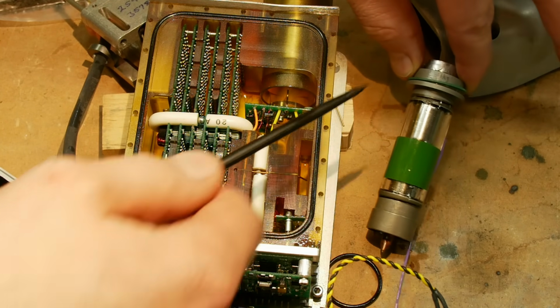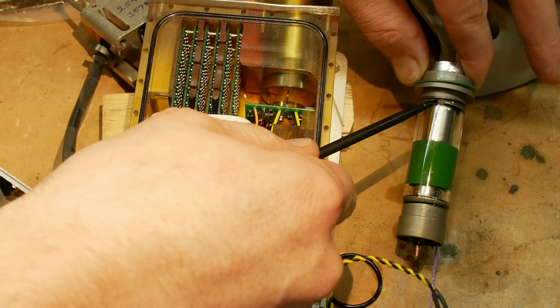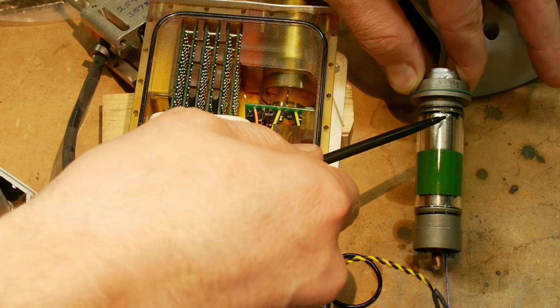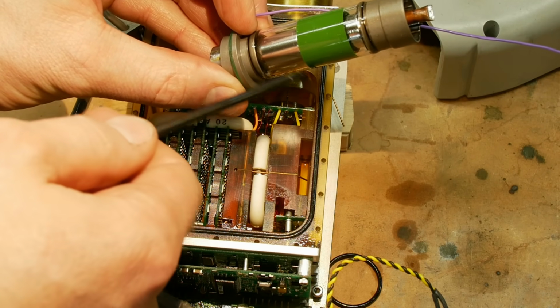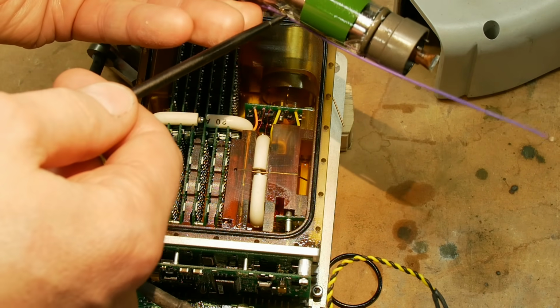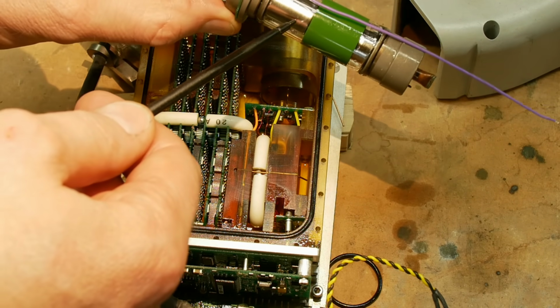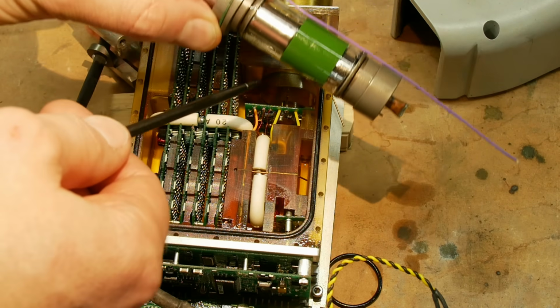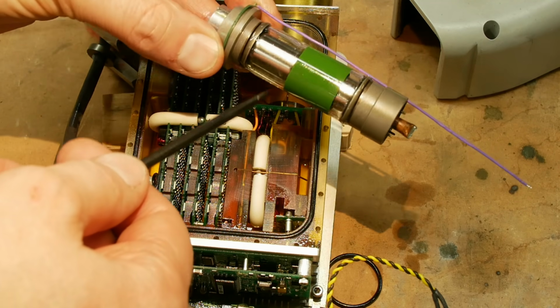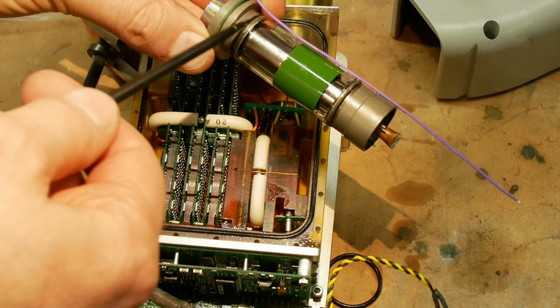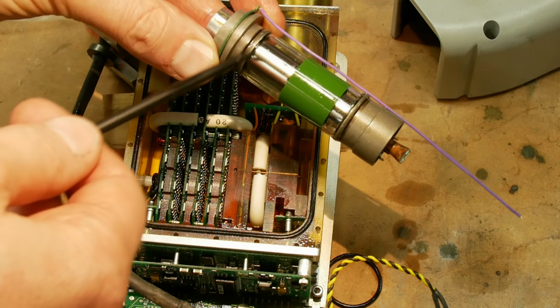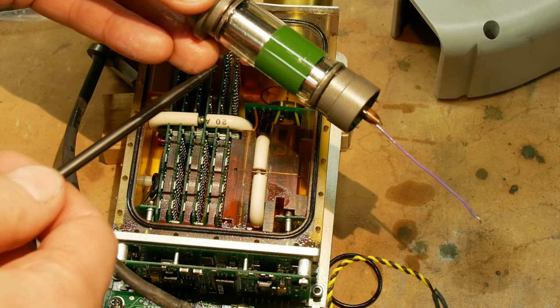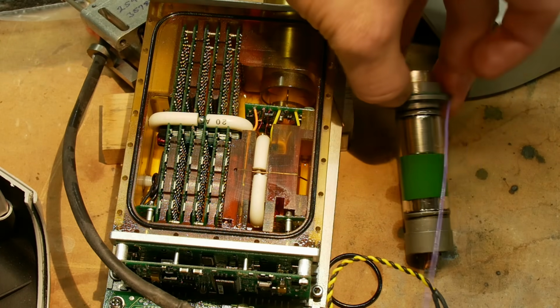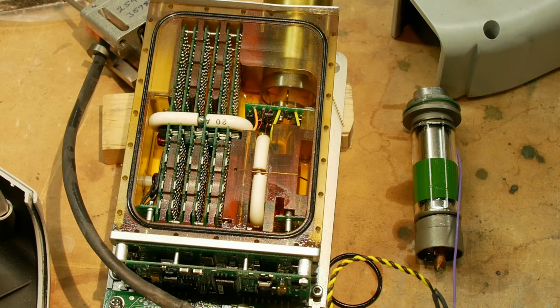And upon closer inspection, there's actually a nick in the glass envelope here. And when I first took this thing apart, I don't know if you can still see it, there were actually a few drops of oil in the tube. Yeah, you can see it right there. So normally there's supposed to be vacuum inside the X-ray tube, and a little bit of a crack there, probably due to some mechanical energy input into it, sucked in the oil, and that was the end of that X-ray tube.